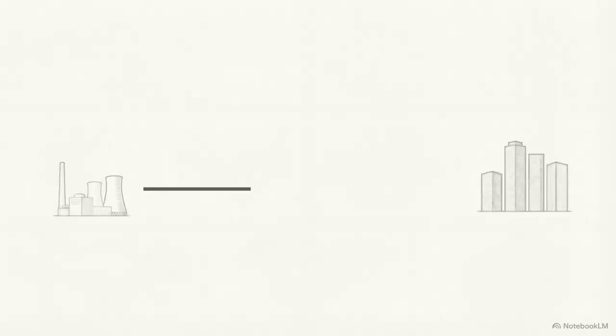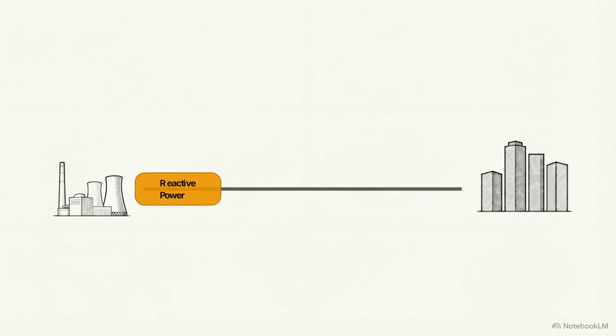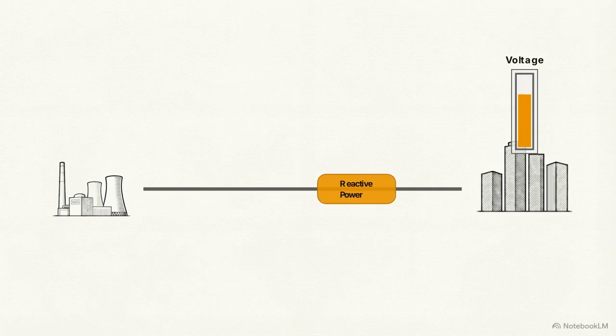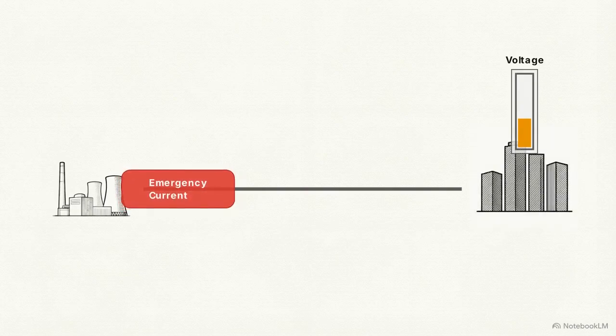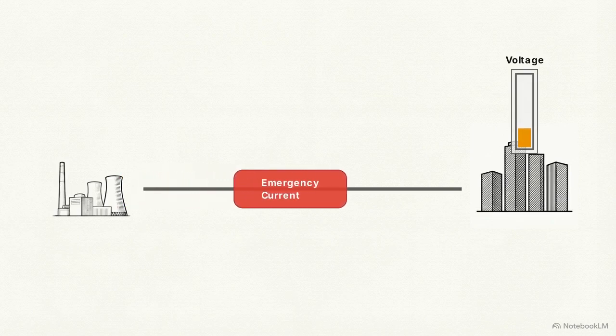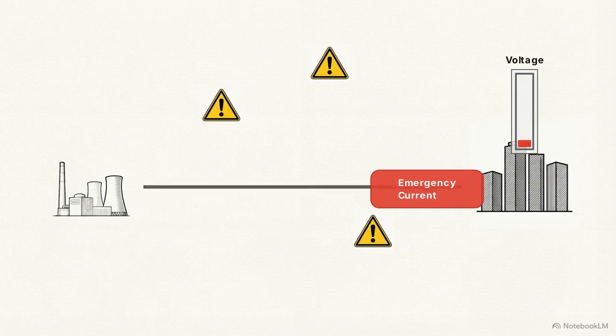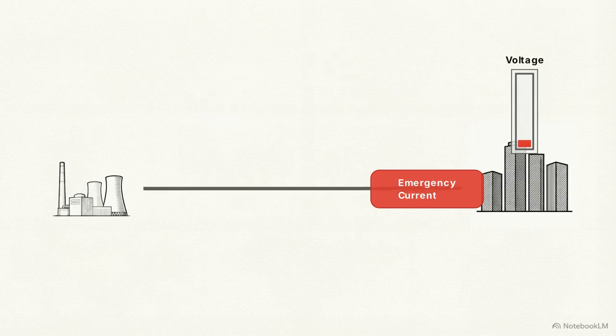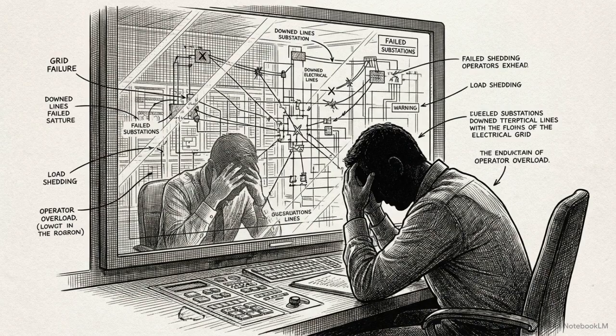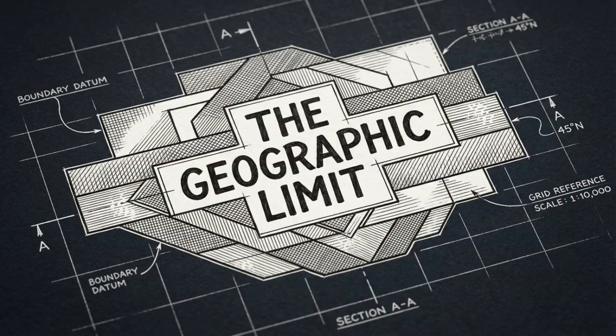Imagine a city demanding a massive amount of reactive power, and the grid operators try to send it from a distant plant across the state. By the time that current reaches the city limits, the voltage on the line has sagged drastically. To push the required energy through at that lower pressure, the system has to draw even more current. That extra current drags the voltage down further, creating a dangerous feedback loop. Eventually, the system buckles. The grid is trying to serve more physical load than the degraded voltage can support. Engineers call this a voltage collapse, and it results in an immediate blackout. You cannot centrally manage reactive power from hundreds of miles away. The physical laws of alternating current make distance the ultimate enemy of voltage stability.